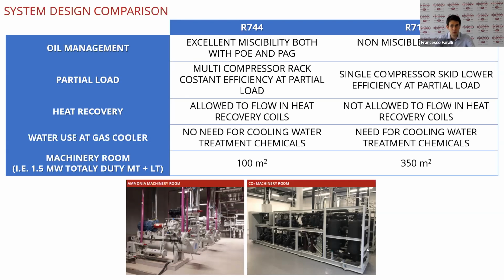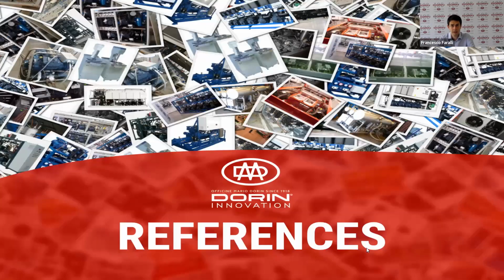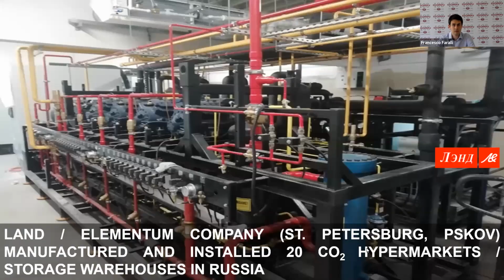We can do heat recovery very easily with CO2 because the safety class is A1, so it's not flammable and not toxic. And in case we have adiabatic cooling at the gas cooler, there is no need for any chemical treatments of the water. Even the size of the machinery room, in case of a 1.5 installation, is much smaller than ammonia. And finally, here are some references, not just for industrial, but let's say some examples.